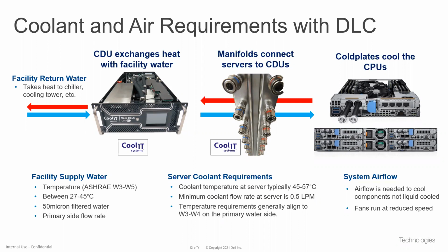The rack manifold is what is connected to the back of the rack. It's almost like a PDU for fluid. It's a vertical manifold that connects to the back of the rack that the servers connect to. The black tubes that come out of the back of each server will connect to the blue cold line, matching the blue connector on the server. The hot return would go to the red connection on the rack manifold and return that fluid back to the heat exchanger.